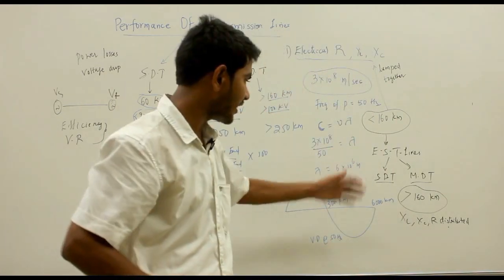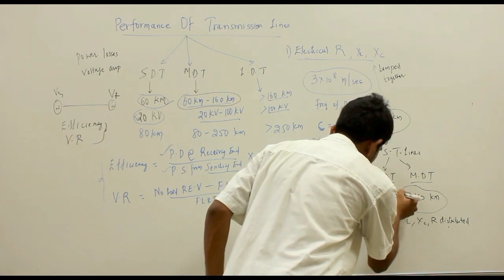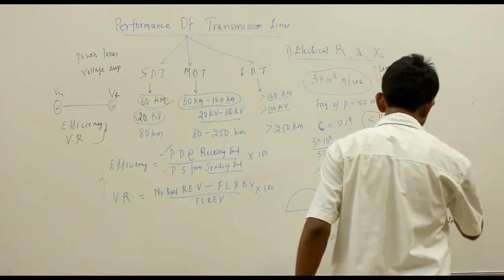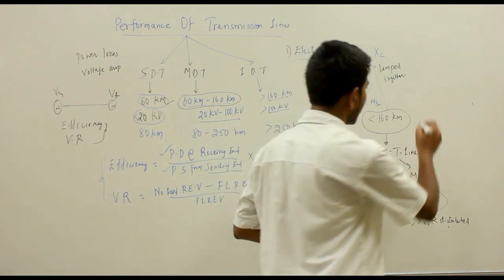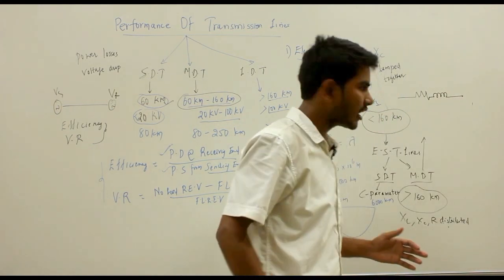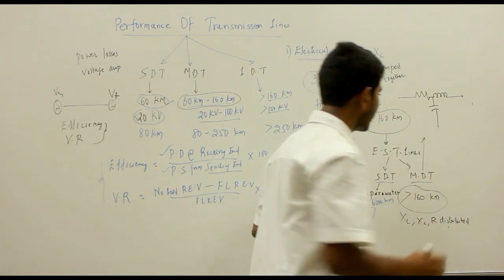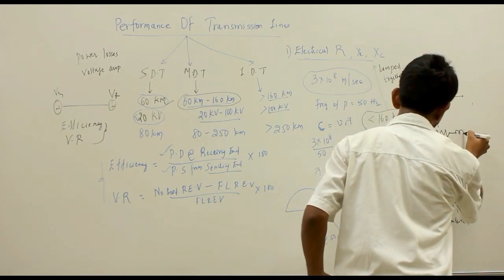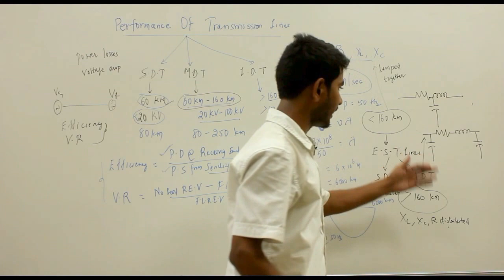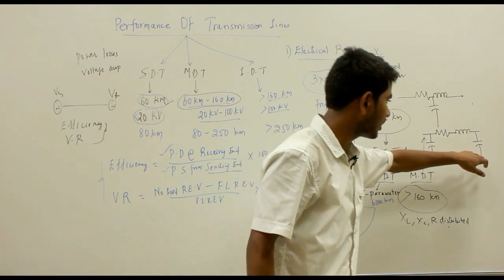In the short distance transmission line, the capacitance parameter is neglected, which is the reason we do not see the Ferranti effect in short distance transmission lines. In the medium distance transmission line, the capacitance is lumped — it can be placed at the middle of the line with resistance and inductance on either side, forming a T-configuration, or each half of the capacitance can be placed at the ends of the line forming a pi configuration.